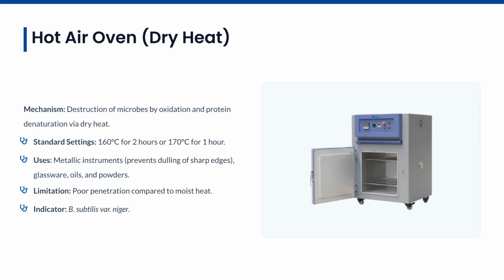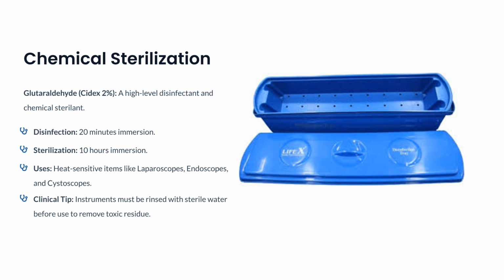It is used for metallic instruments, glassware, oils, and powders. Its main limitation is poor penetration. Chemical sterilization primarily uses glutaraldehyde. This is a high-level disinfectant. Disinfection takes 20 minutes, while sterilization requires 10 hours of immersion. It is ideal for heat-sensitive items like endoscopes. Instruments must be rinsed with sterile water to remove toxic residue.